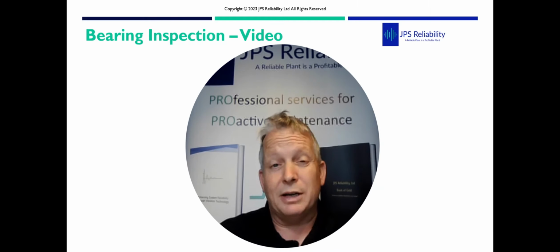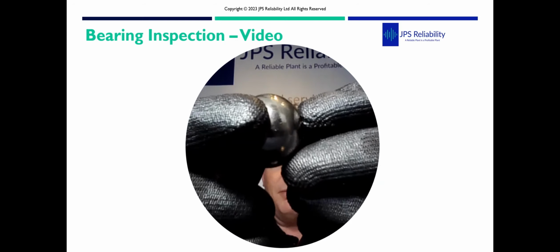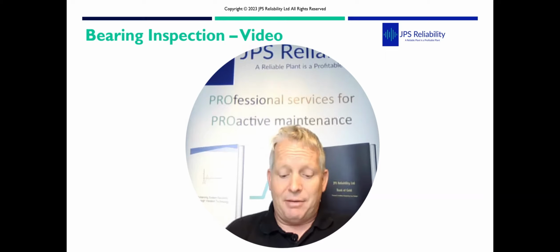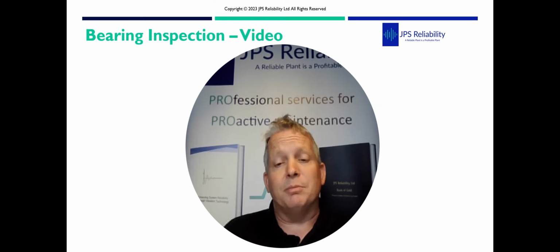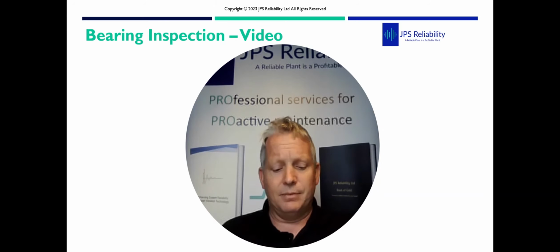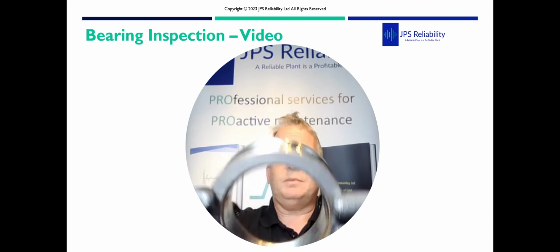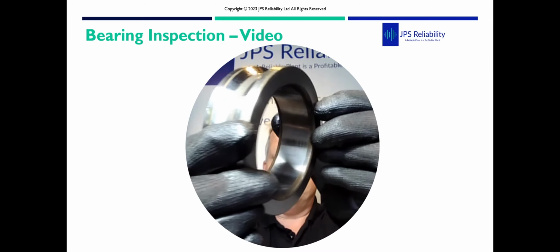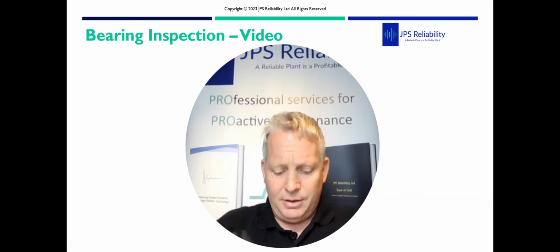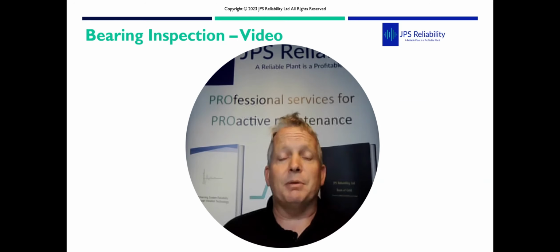Now on the balls themselves, it's hard to see, but if you look on there, you can capture dull stripes. The dull stripes are where, as the ball's spinning, that's a contact path, and that is where the EDM is starting to build up a capacitor, breaks the grease down, arcs through and gets back to the transformer. This is the inner raceway, so you can see it's offset. The inner part of the inner raceway is perfect, no fretting at all, and you can see that it's slightly offset. As I say, we're going to try and do some more of these. This is the bearing in question.